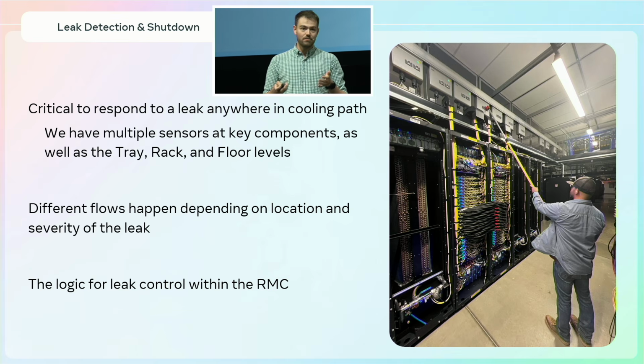So we essentially have a trade-off where we know where the different sensors are. Some correspond to really small leaks, or maybe just residual liquid left in from manufacturing, and in those cases we might just shut off the sled, or a couple of components, versus shutting off the whole rack. But obviously, if you do have a bigger leak, you want to make sure you're being safe and everything goes off.